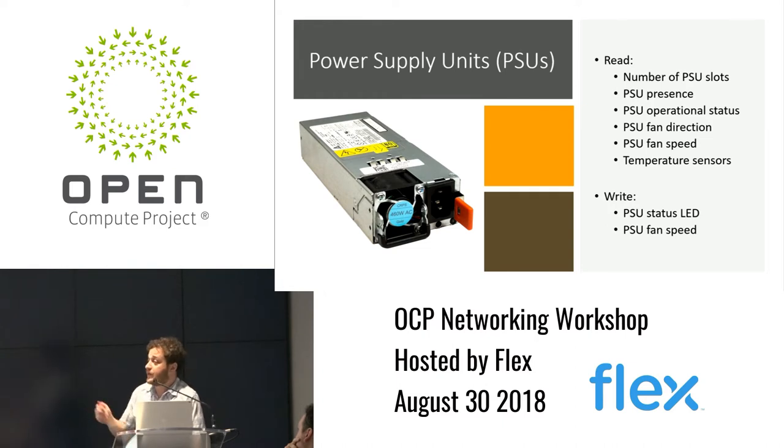PSU fan direction. Each PSU has a fan to cool itself down. We need to make sure we have the fan direction. Is it an intake fan or exhaust fan? Do we know what we intend it to be, and does that match? PSU fan speed, of course, same thing. We need to make sure that this fan is operating as we expect it to and keeping that power supply cool. And in order to do that, we also need to access the temperature sensors inside the power supply.